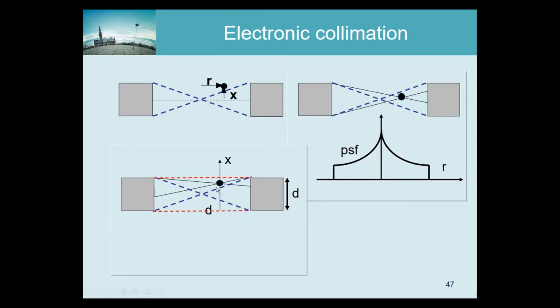But as soon as the source passes the dashed line, both detectors become a bottleneck — one is a bottleneck for the lower line, and the other becomes a bottleneck for the upper line. Moving the point source from the dashed line to the red line, the sensitivity decreases linearly.